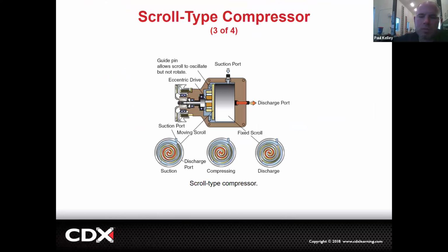Now, getting away from piston types, we've got scroll types. I'll show you one of these. This is kind of oblong. It'll go around like this, basically have an open port, suck refrigerant in, squeeze it down, push it out, squeeze it down, push it out, squeeze it down, push it out. So you can see it pulls in here and it pushes out here. These wear as well. These also have a type of ring, but it's not a piston ring - it's more like a sealing ring in the shape of some of these scrolls.